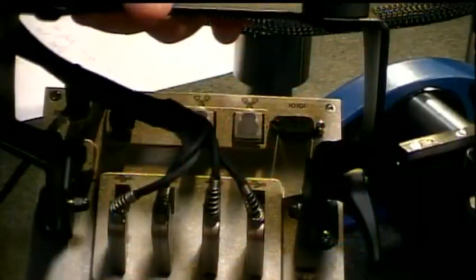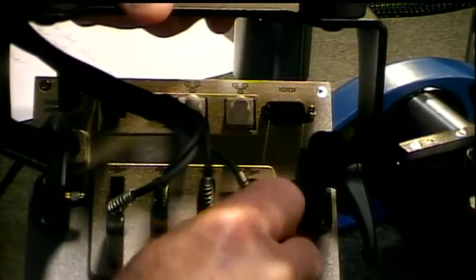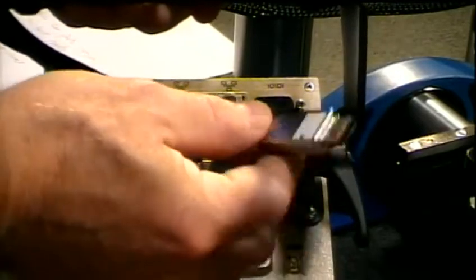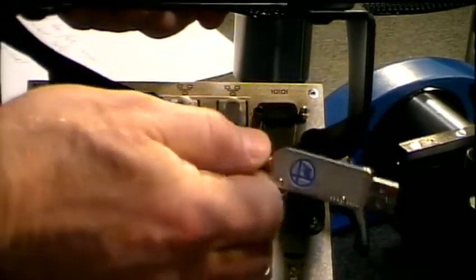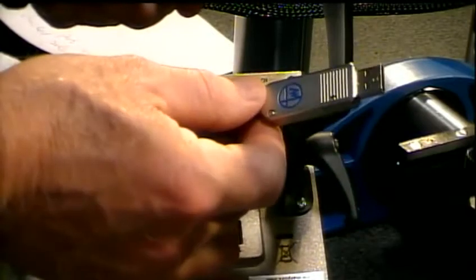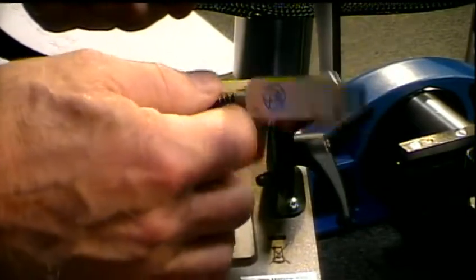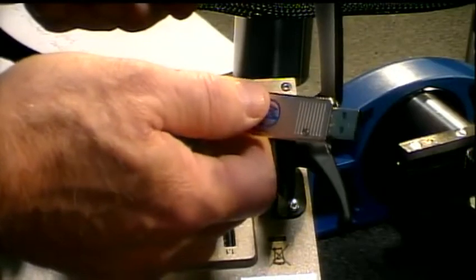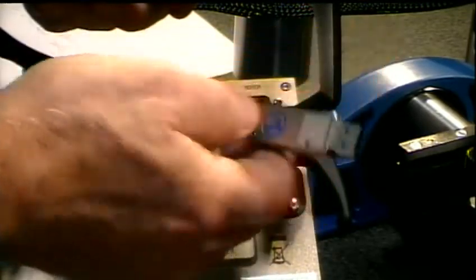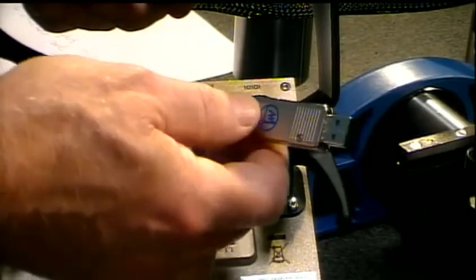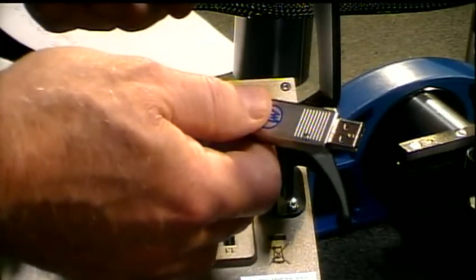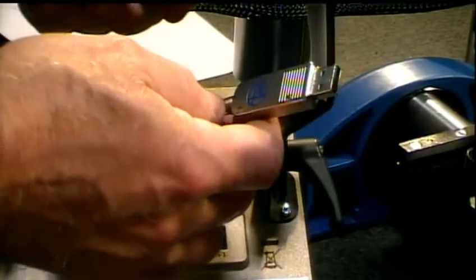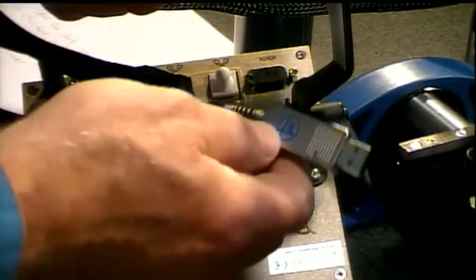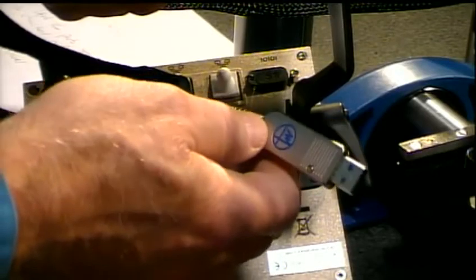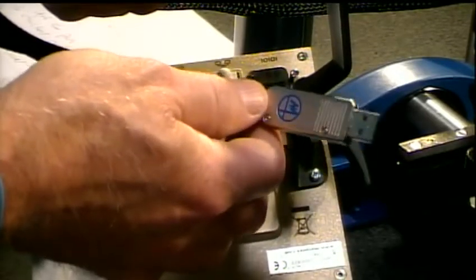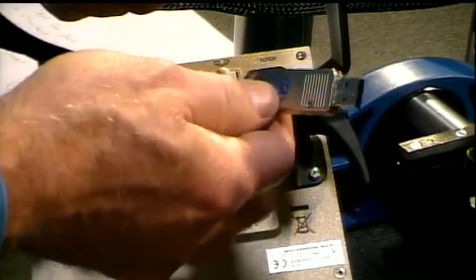If we can come back to the Nemo, I'm going to unplug one of these. Okay, this is the end of the probe itself. It looks like just your regular standard USB connector, but inside this case there's electronics. An LVDT probe is an analog probe—the output is analog, and in order to go to something digital like USB, it needs to be converted to digital. So inside this case is an A to D converter to convert the analog LVDT probe signal into a digital signal. Also in here is the electronics for correcting small linear and sensitivity errors inherent in an LVDT probe.